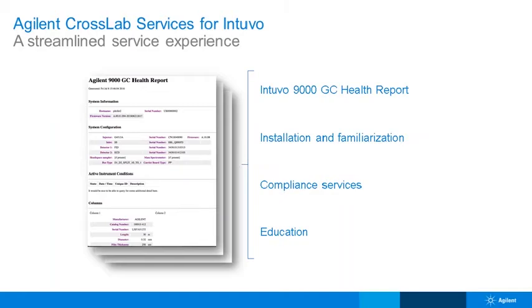With the new range of GCs, whether it be the Intuvo or the 8860 or the 8890, you have those dual-core processors on board, and that means they're monitoring all the settings. So you've got a health report that can be produced from any of these GCs. And this will either be proof that the GC is working absolutely perfectly, or should there be a problem, then you can download that health report onto a USB and email that to Agilent, and we know exactly what's wrong with your instrument, which means that you're going to get first-time fixes. This speeds up everything for you, the user, and also for us, the supplier of the instrumentation. It's just a much more modern way of going about fixing instrumentation.